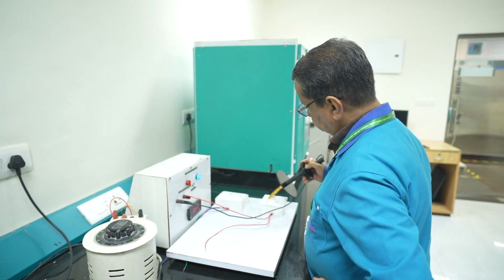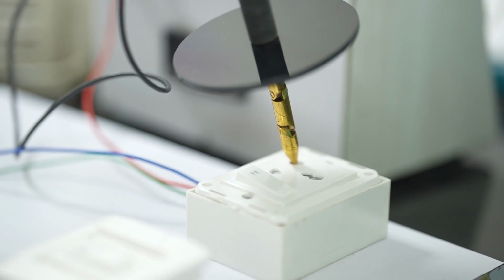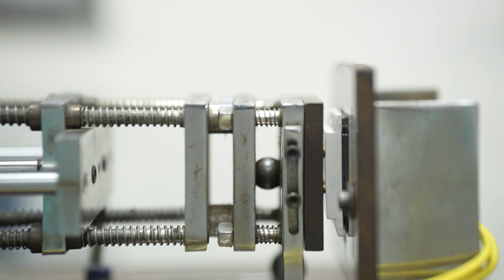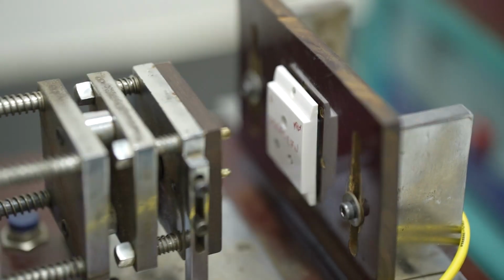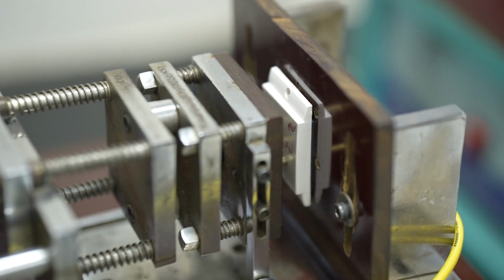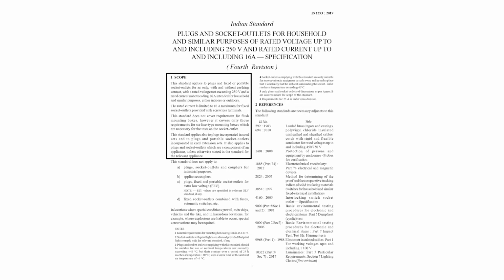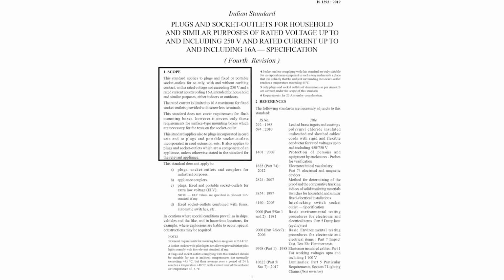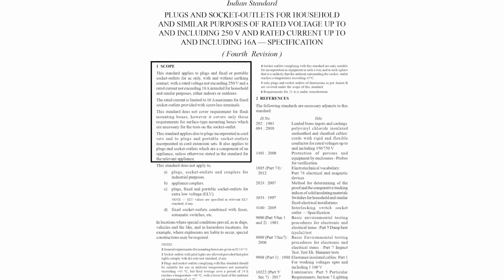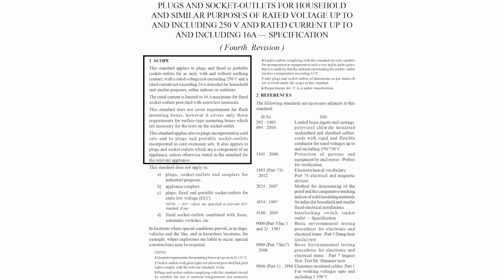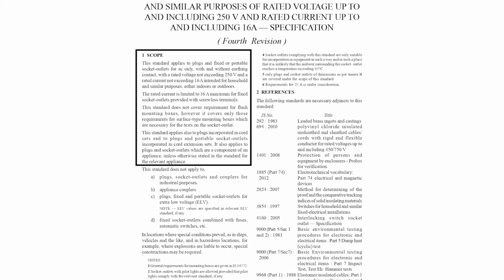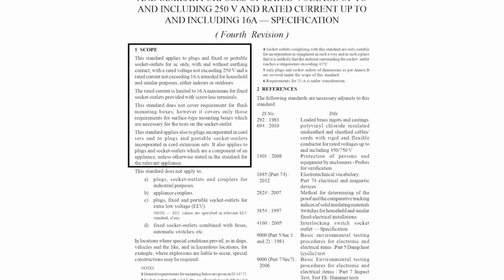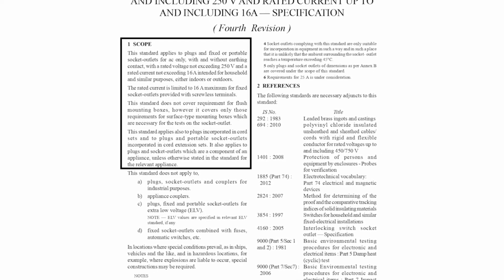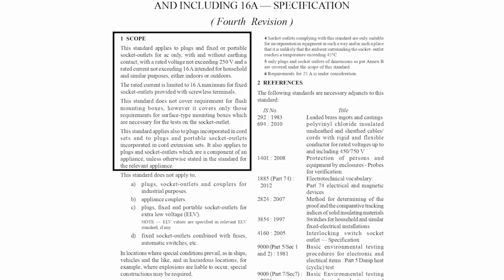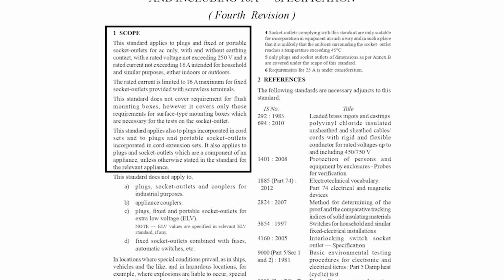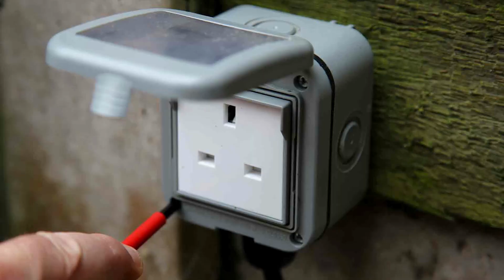The step-by-step testing process, including safety, durability, and electrical performance, is covered to ensure compliance with Indian standards. This standard is applicable to plugs and both fixed and portable socket outlets designed for AC use with or without earthing contact and with a rated voltage not exceeding 250 volt and a rated current not exceeding 16 ampere. These are intended for household and similar purposes for both indoor and outdoor use.